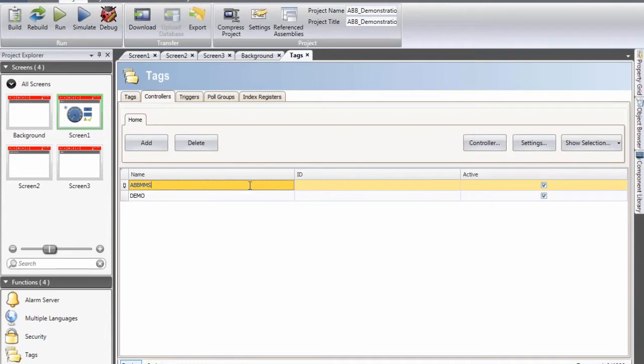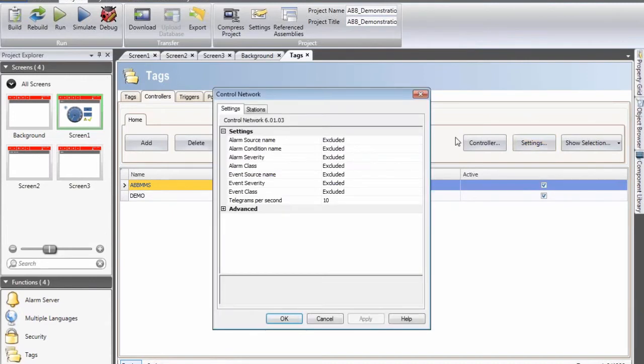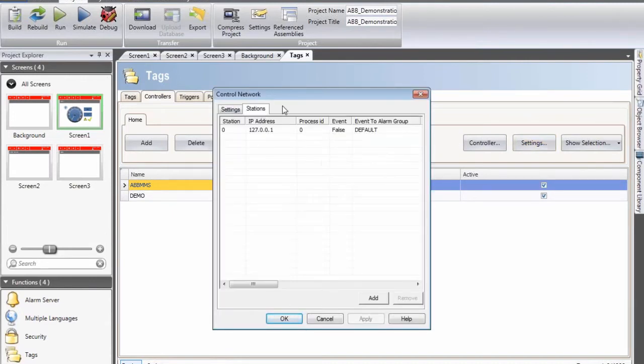The next step is to configure the driver. We need to tell it which IP address it should communicate with. So I select my ABBMMS driver and then followed by settings. I need to define which IP address my soft controller is running on, so it will be 127.0.0.1 with a process ID of 0.